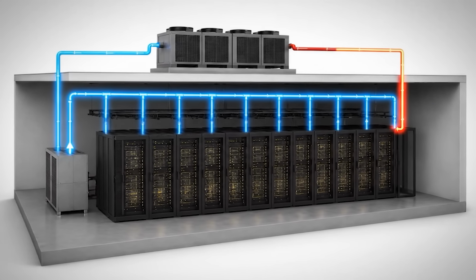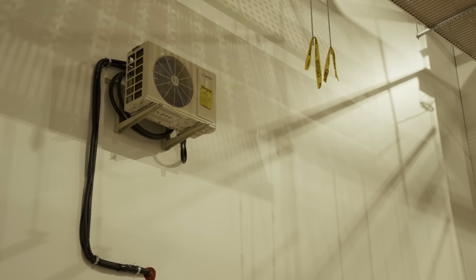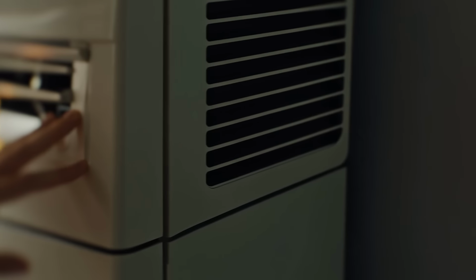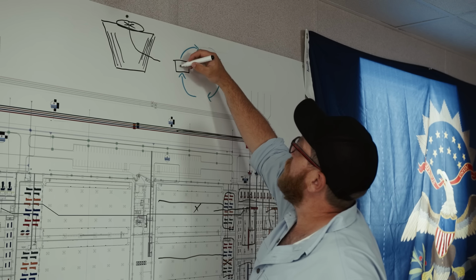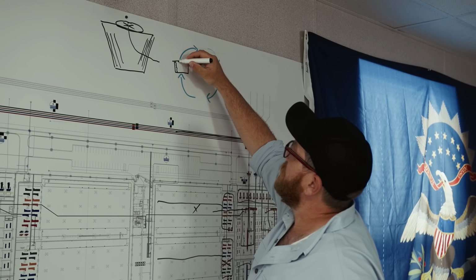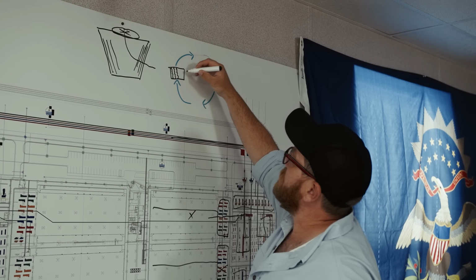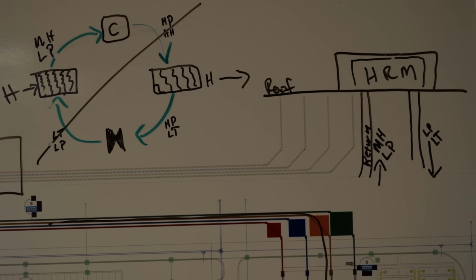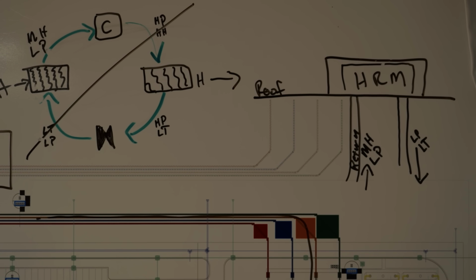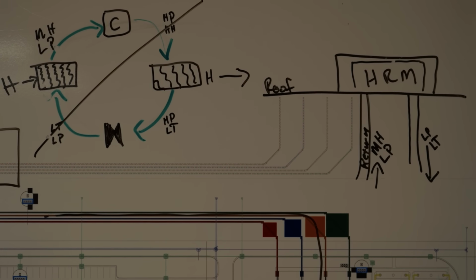We have closed loop cooling systems, which kind of helps to think of it like the air conditioner on your house, we just have a lot of them, and they're very big. So instead of taking an open loop and dumping water across media and blowing air across it to bring the temperature down, it stays in coils, just like the fins on the radiator on your car. We're doing the same, blowing air across it to bring the temperature down, then cycling that cooled water back into the building where it goes through the refrigeration cycle in the chiller and gets brought down even further to our target range.